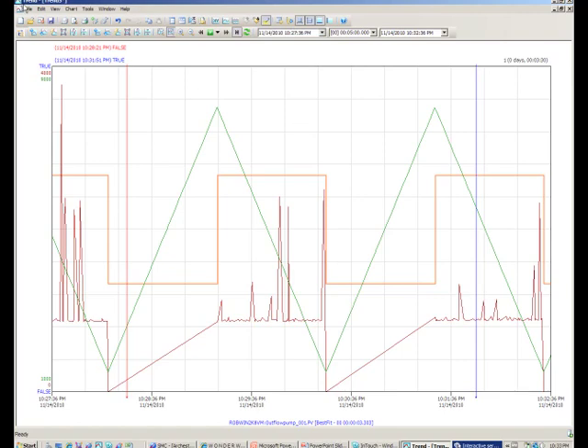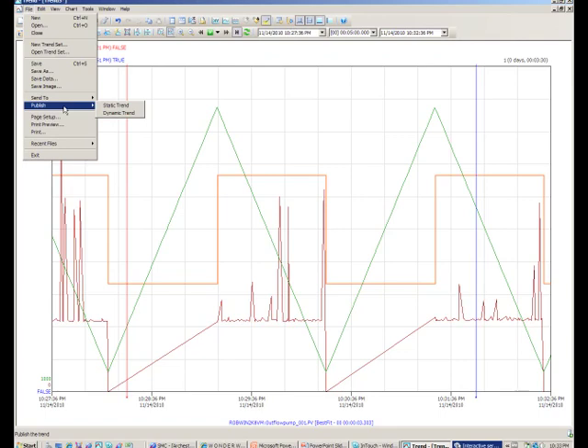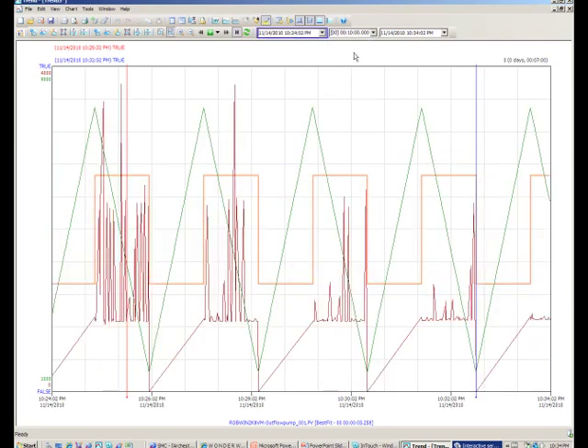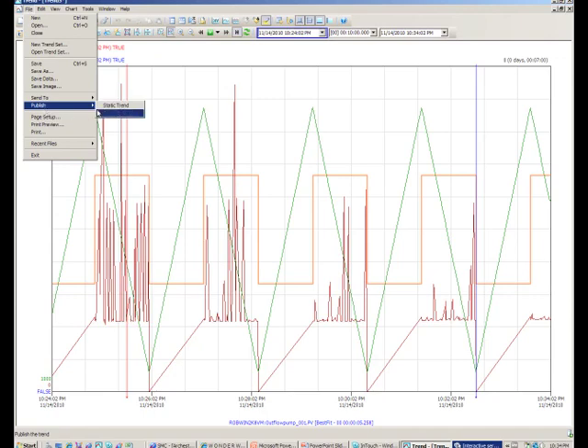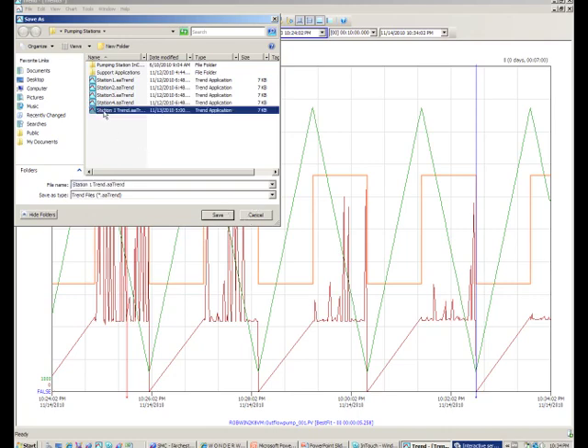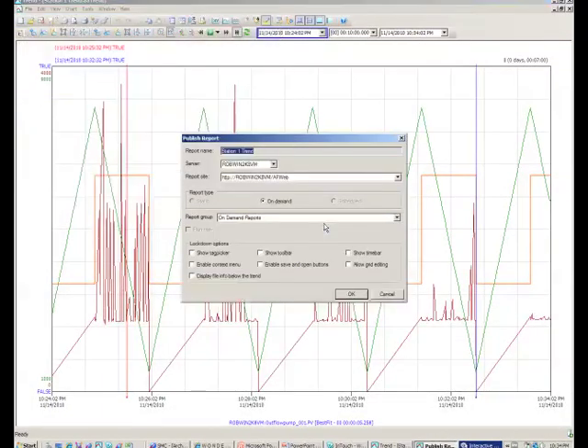So the next thing I'm going to do is I'm going to actually publish it so if I say publish I have the option of publishing it as a static trend or a dynamic trend. If I publish it as a static trend it's simply a snapshot in time of what took place in the process. If I publish it as a dynamic trend it means that when the user opens it he looks at for example right now we're set for five minutes so we'll change that, we'll make it ten minutes as we did the last time. And what we'll do is we'll go back to publish and we'll publish it as a dynamic trend, and the first thing it wants me to do is it wants me to save it. So I'm going to call it the station one trend and save and I say yes I do want to replace the existing one and now I have to publish this.